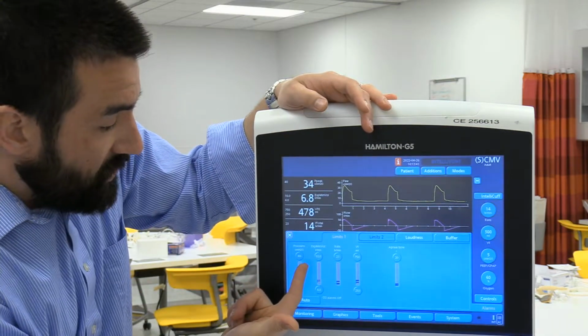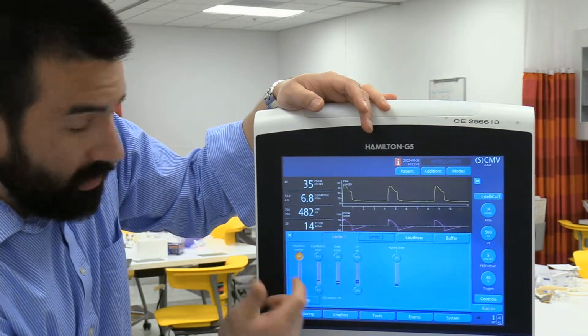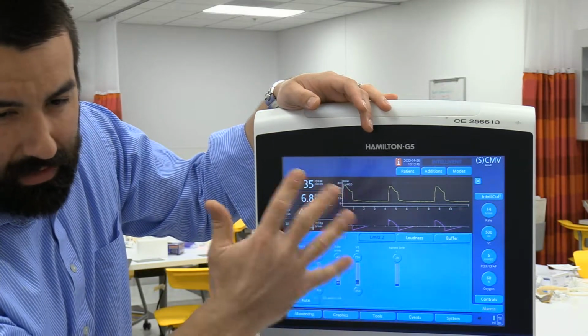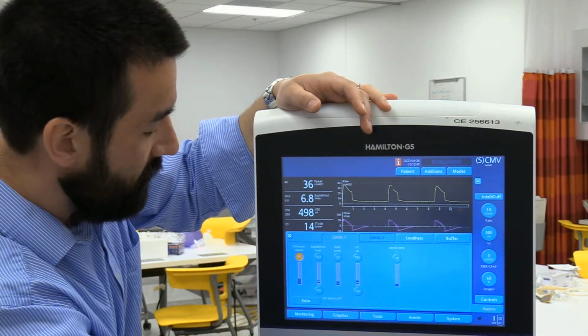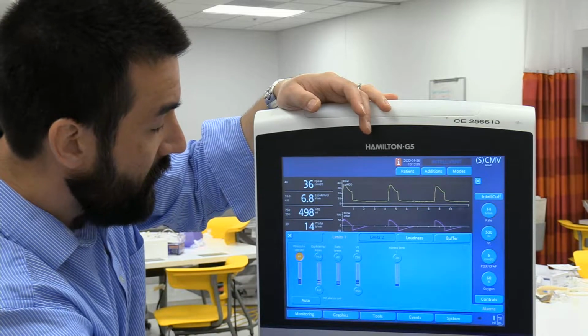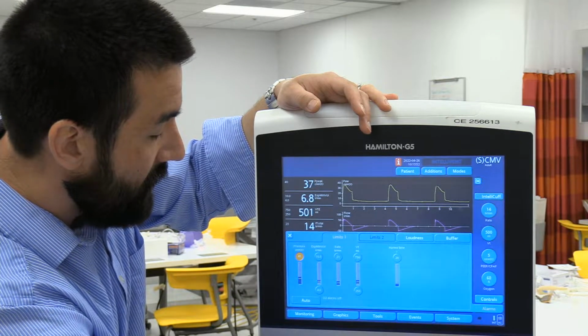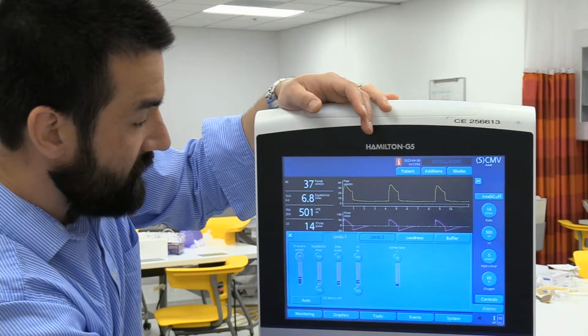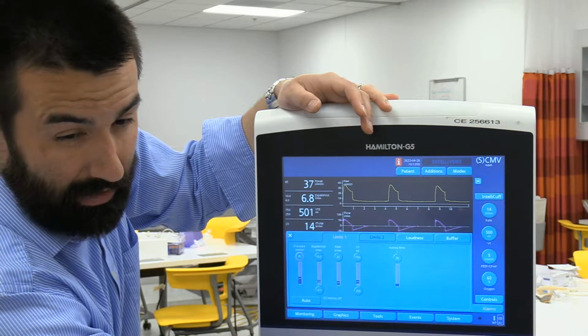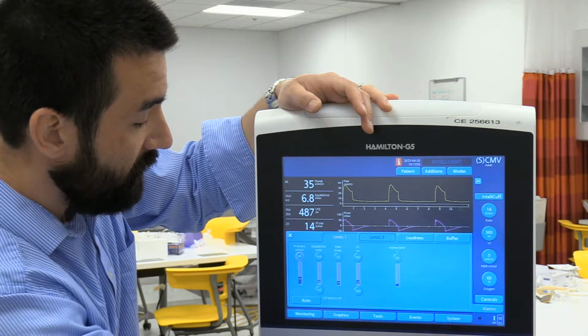You've got your high pressure, typically 10 to 15 centimeters of water above in this type of mode, and in PRVC sometimes, or APV, we'd have to consider another little bit of a buffer. So I could go up. I don't want it too tight. I'm already at 35, 36, 37 centimeters of water, so I could set this a little tighter. 45, 40 would be a little too tight.